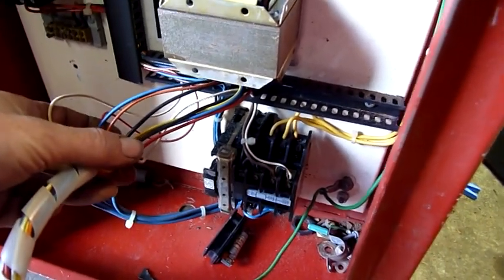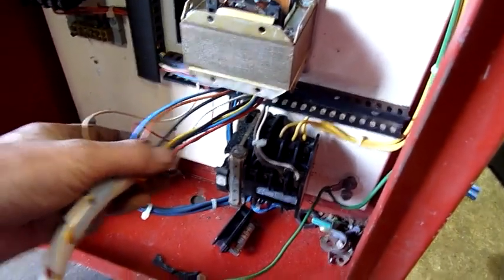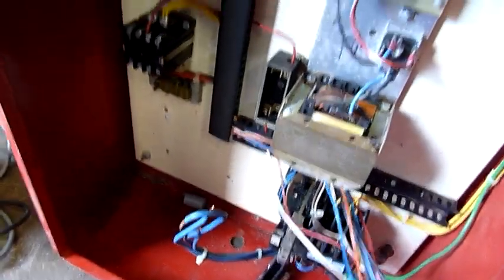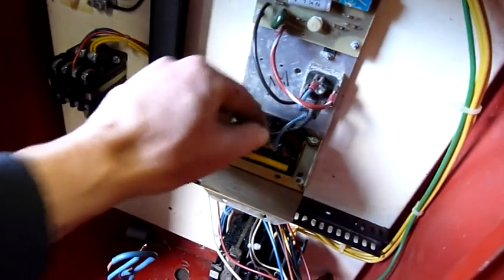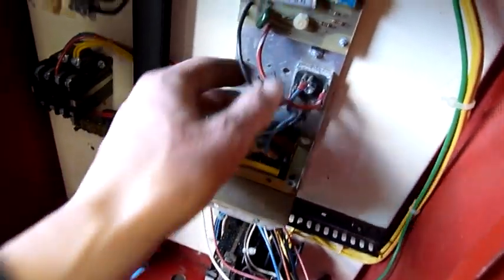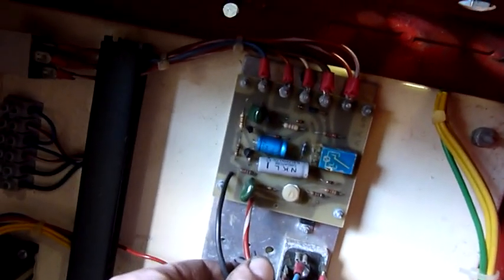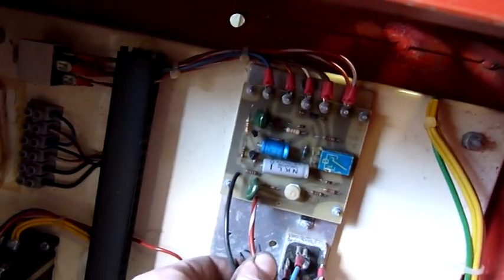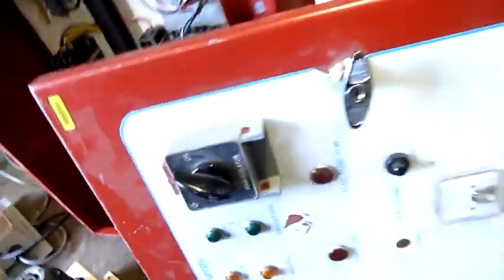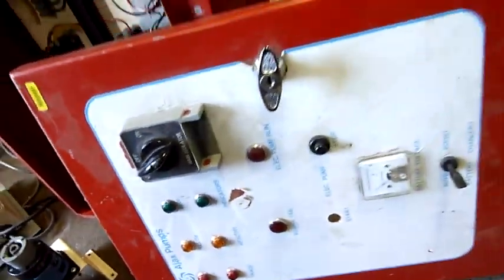There's a nice big contactor there — looks like a 25-amp contactor. It's an old one but still good. It's got a 240-volt coil in it. That 12-volt transformer is completely nuked — it's gone. There's a little control board in there with some fairly old componentry. This is probably 1970s, although the selector switch is a bit newer.